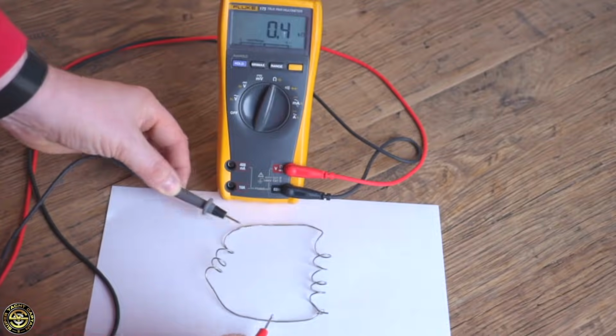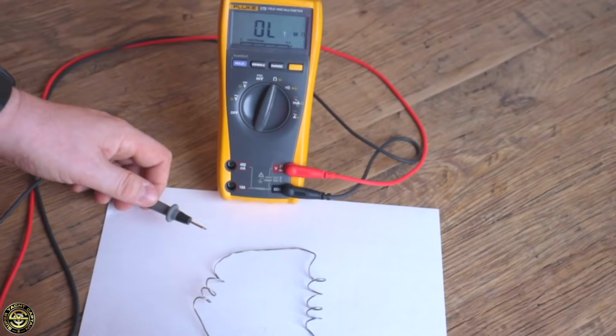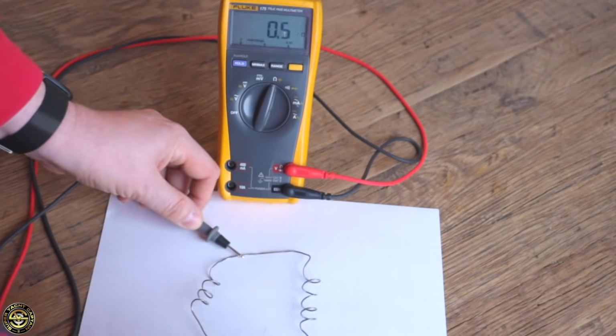In the report, they said that prior to energizing the load bank, turning on the power, they measured the resistance between the load bank earth and the true earth, and it was measured at 105,000 ohms. Now, in our test with our good circuit, it only requires 0.5 ohms. This was 100,000 ohms, very high resistance. So there was obviously an issue with the earth cable. Maybe it was frayed, or it was partially broken.